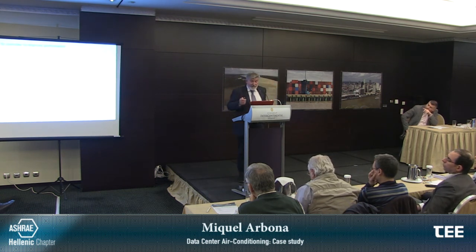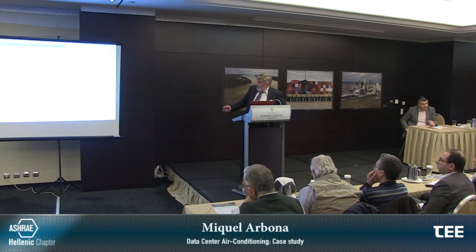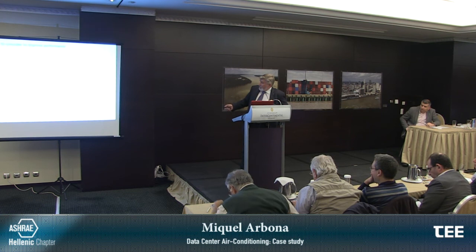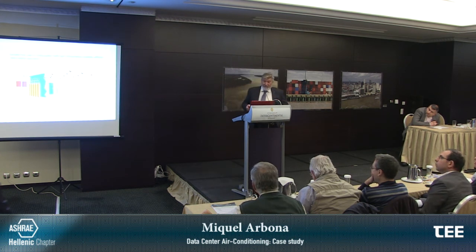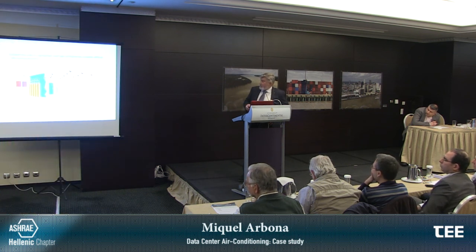And also it's very important to work with IT people and be sure that when they get into the data center, they close all the holes and avoid bypasses, so that the air, when it comes into the IT room, doesn't go from the supply to the return without doing anything. So it's important to have all the holes closed and not have recirculation and not have bypass. But this is not our job, but the job of the people inside the IT rooms. Of course, it's also interesting that you can use this system in combination with a gas extinguisher system because it's always the same air, so it's not interrupting the system.